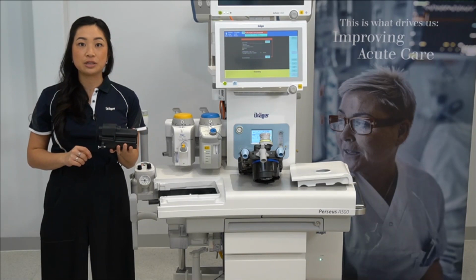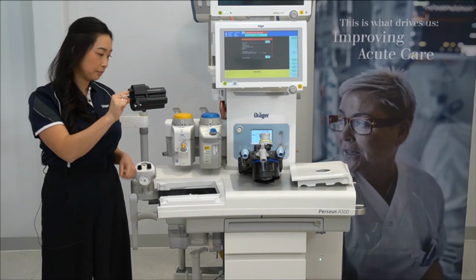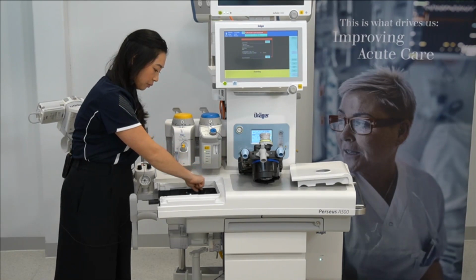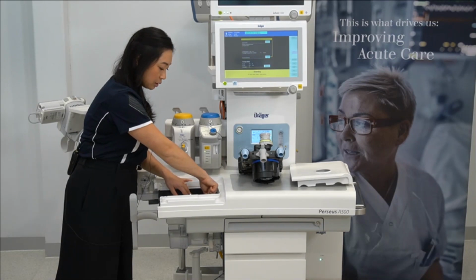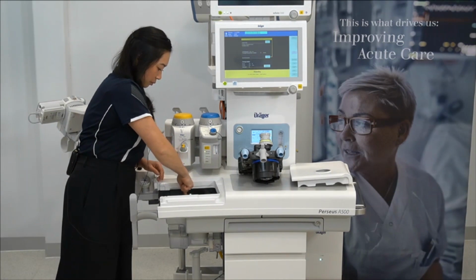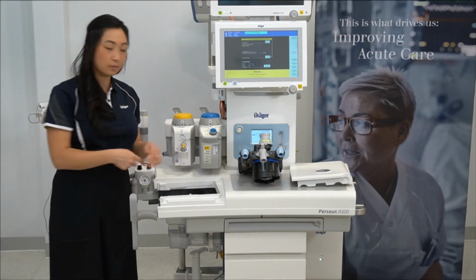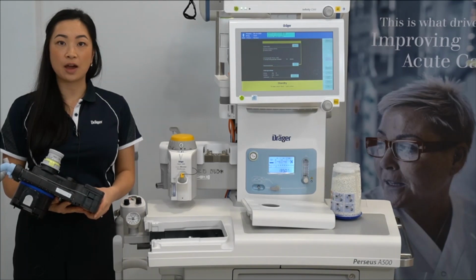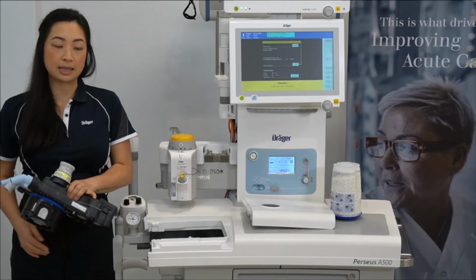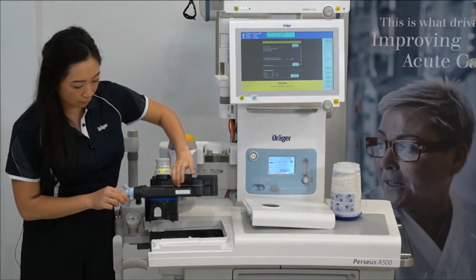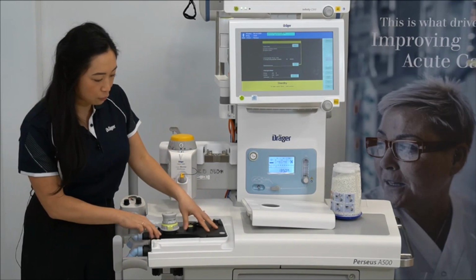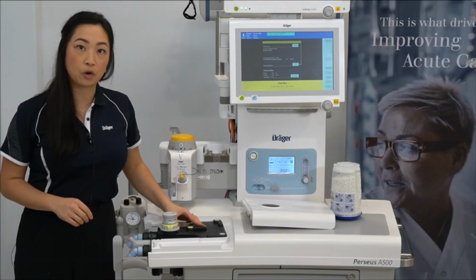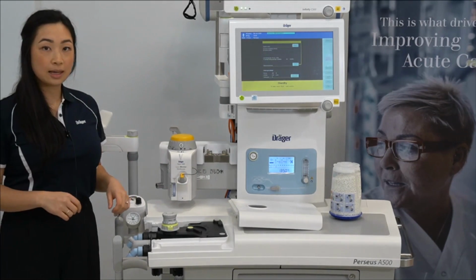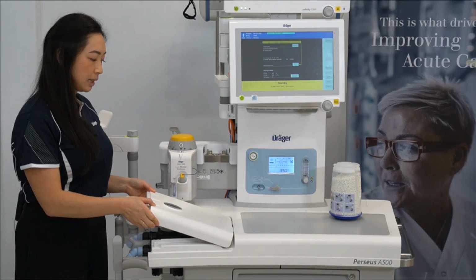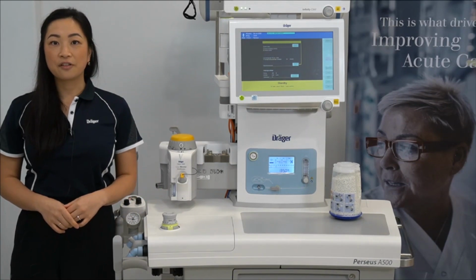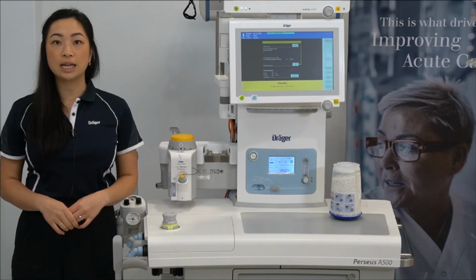To return the ventilator to the device, place 2 fingers in the hole of the turbine and align it up with the hole, and then push down with your thumb on the screws and turn as you go. To return the breathing system back to the device, place your finger on the finger grips on the top of the breathing system and align the click adapter up with the hole. And then firmly push down, which will then allow you to push the green lever forward to lock the breathing system in place. This will then allow you to replace the breathing system lid. For further information, please refer to the instructions for use or contact your local Dräger representative.